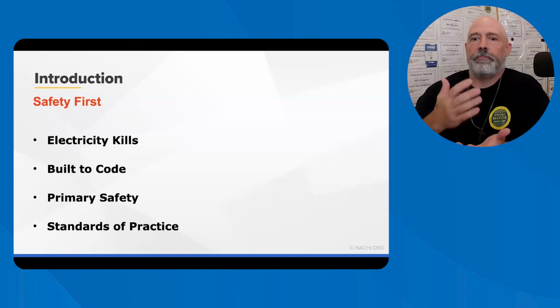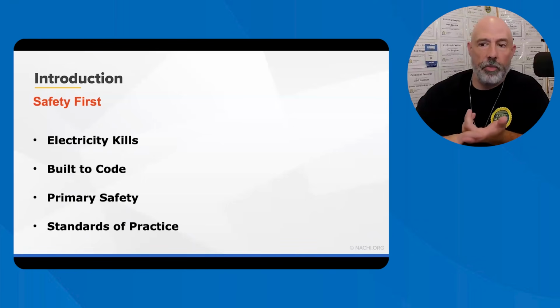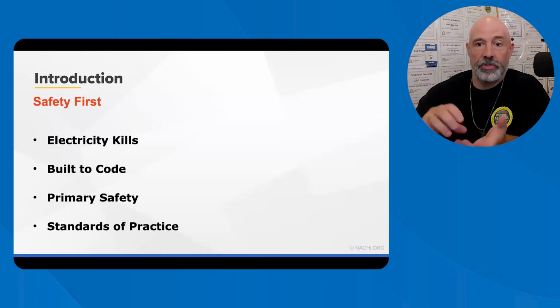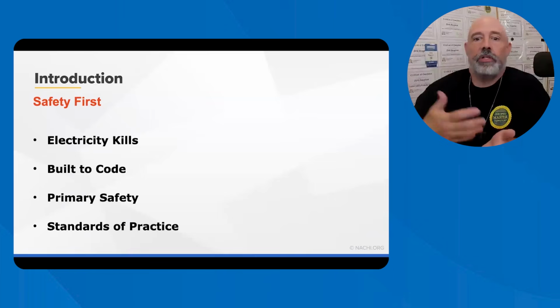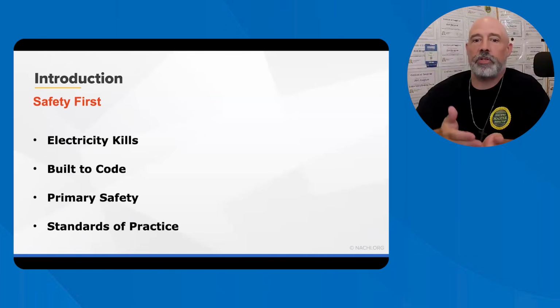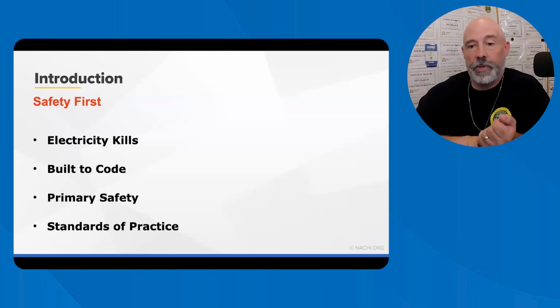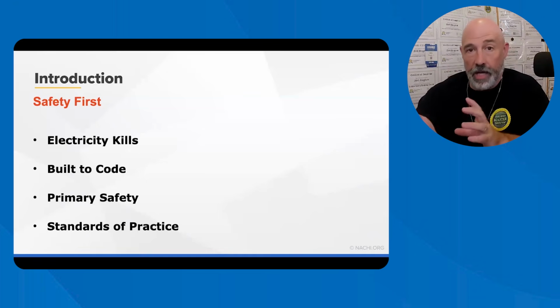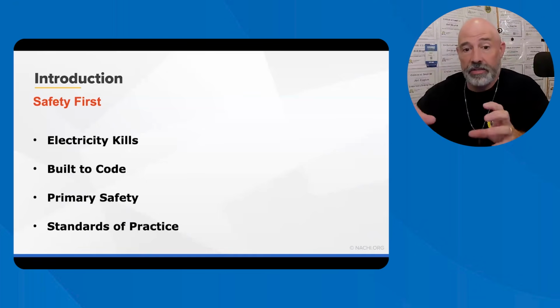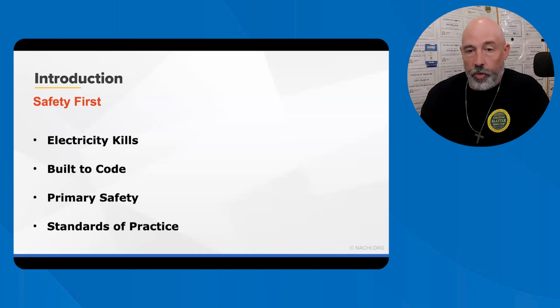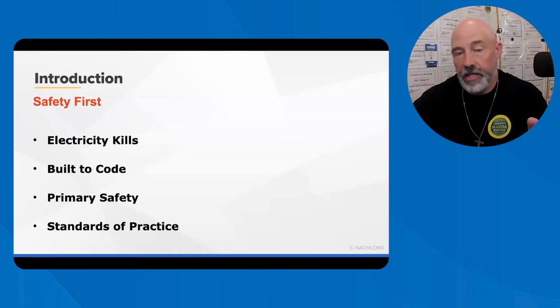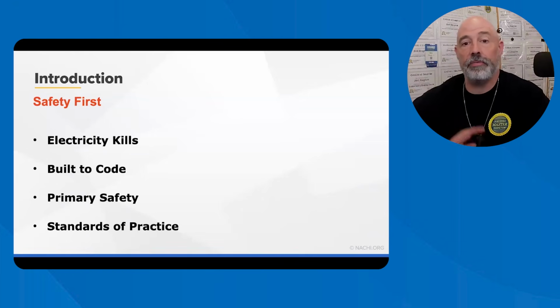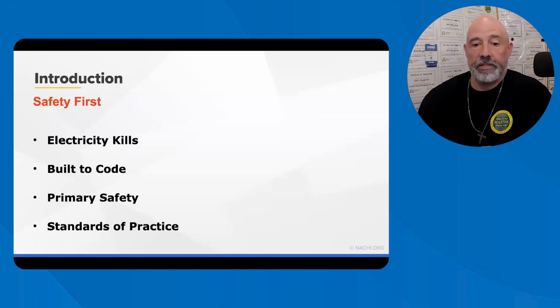And the home inspector should be especially cautious when evaluating the panel boards, electrical system and distribution panels because they can kill people. According to the InterNACHI home inspection standards of practice, a home inspector is not required to do anything that the home inspector feels is unsafe, including removing dead front electrical cabinets or panel boards or exposing electrified or live electrical components. So safety is number one. A lot of you, especially those in Florida, have the 4-point inspection where you're supposed to take off the panel board. If you feel unsafe, don't do it. Just say, this feels unsafe. Recommend a further evaluation from a licensed electrician.